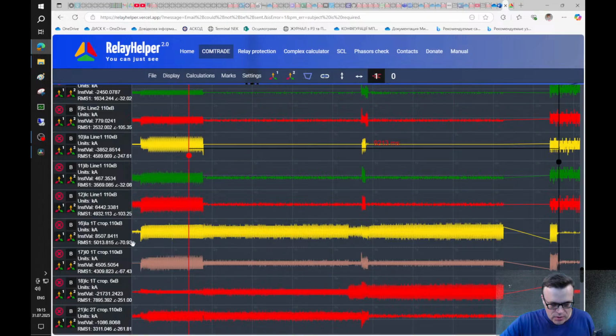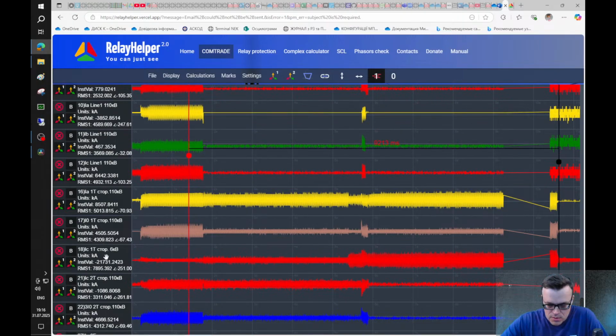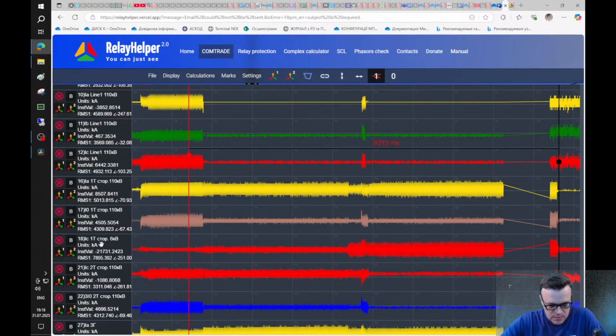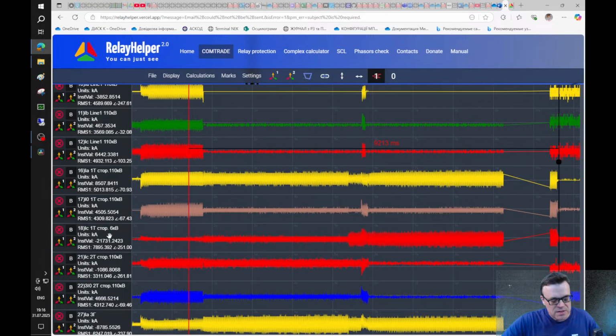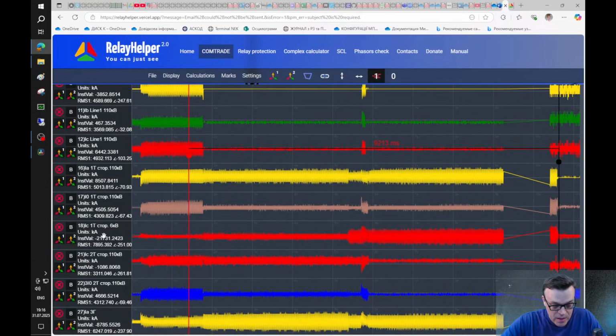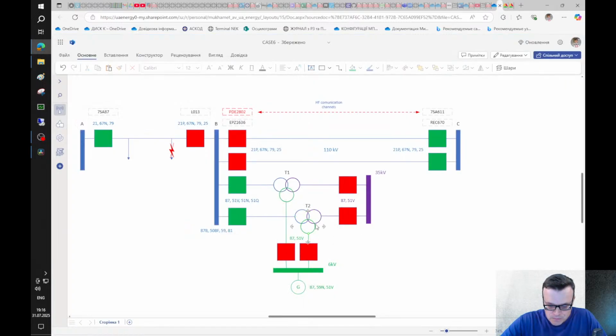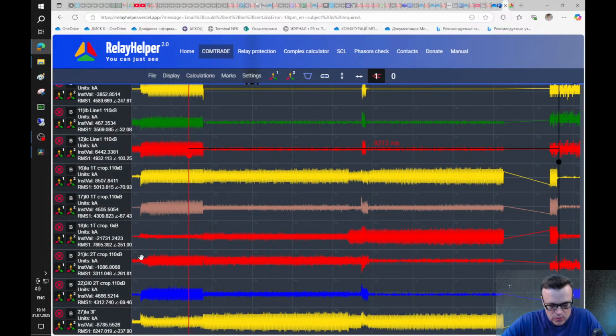This is 2 currents from first transformer, and one channel is phase A from the 110 kilovolt side, and this is zero sequence current of that transformer. I believe I made a mistake by naming this one. Oh no, this is current from a 6 kilovolt line. And these two channels are currents from second transformer from phase C of 110 kilovolt side, and also zero sequence current from 110 kilovolt side.